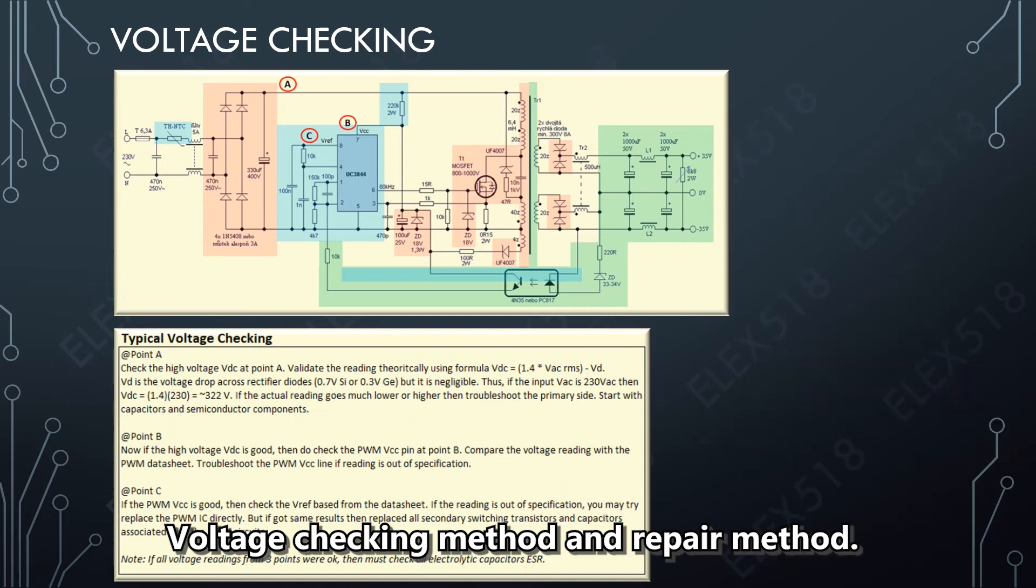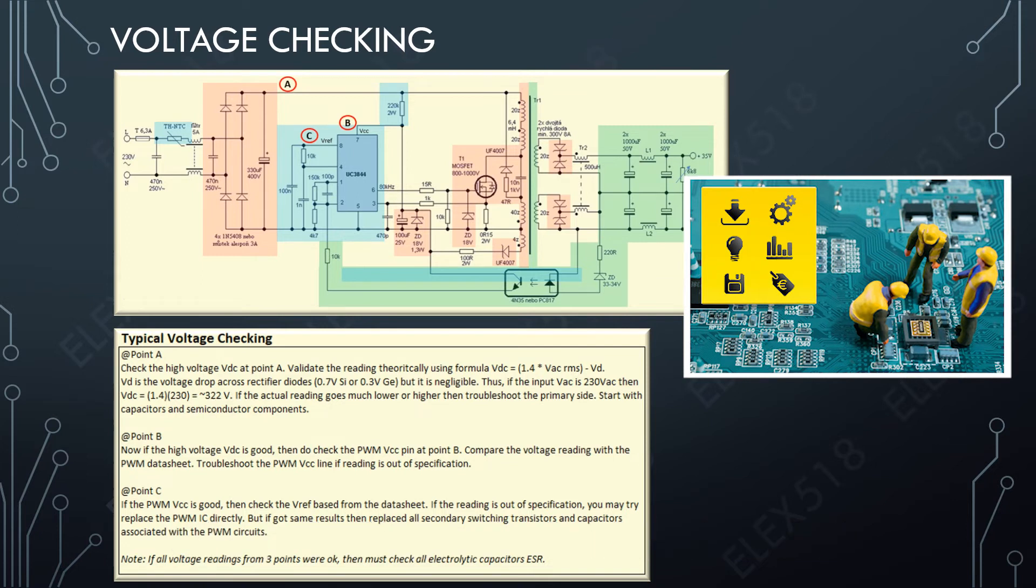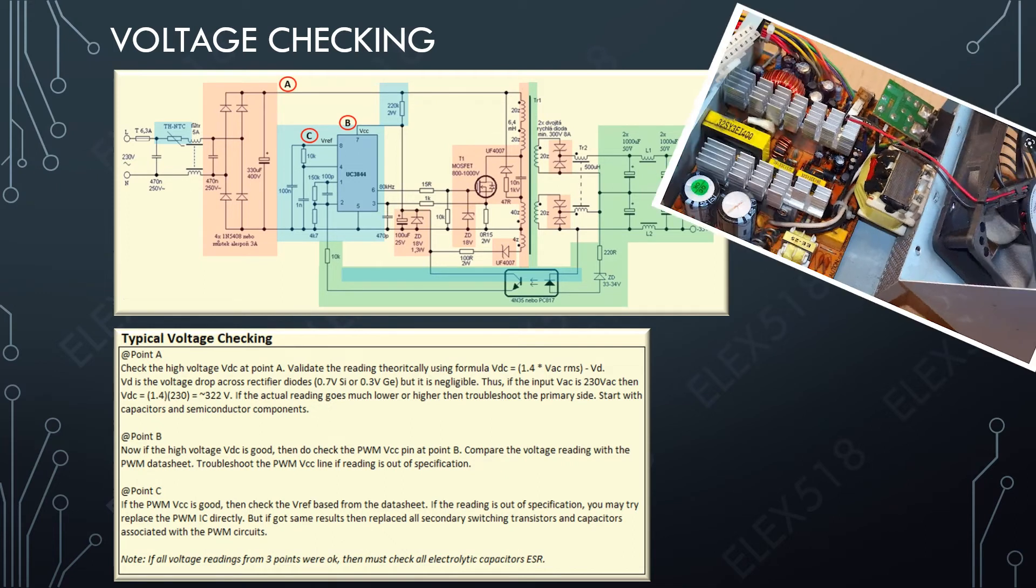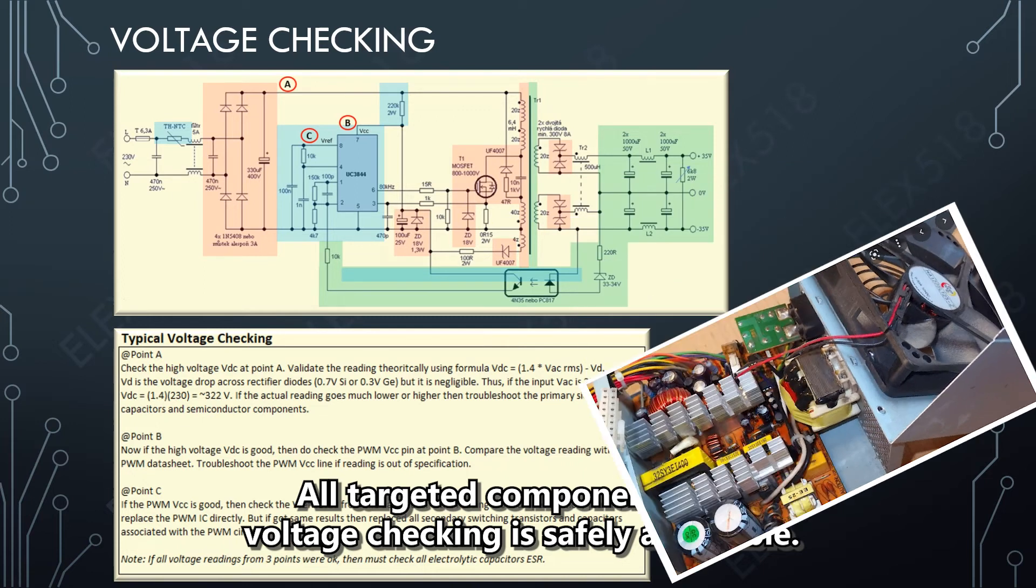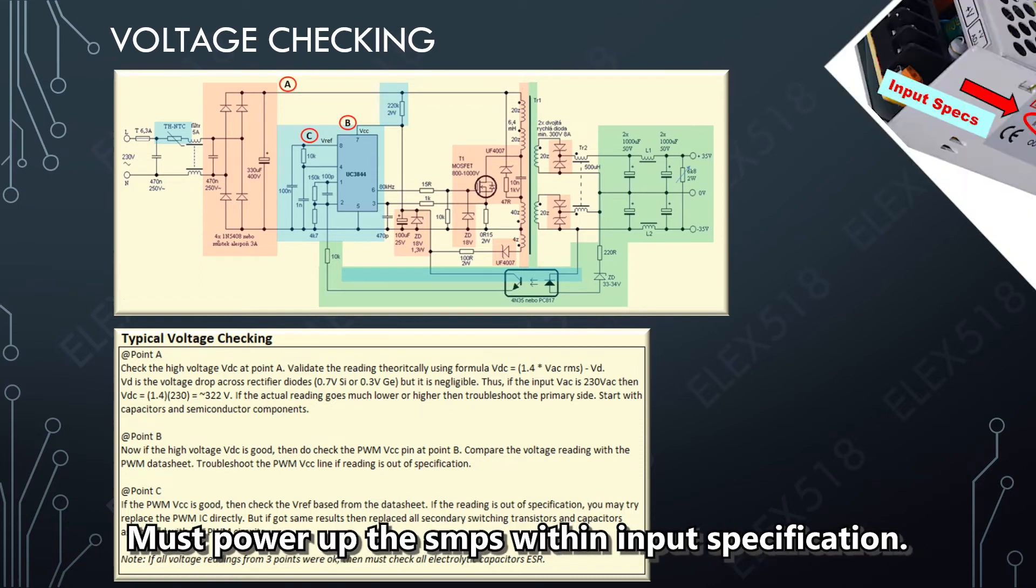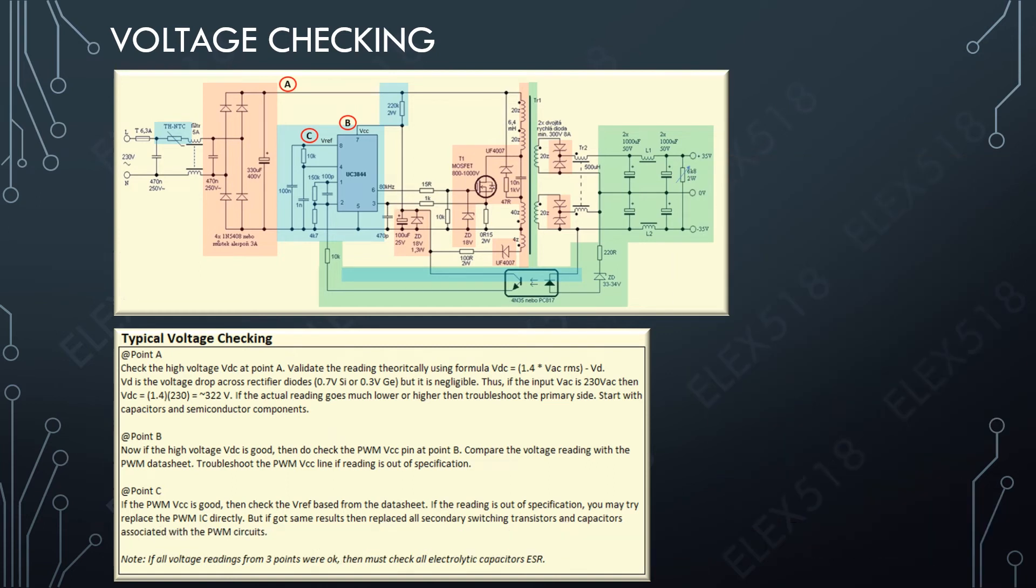In this slide I want to share the initial voltage checking and repair flow that we do before we go deeper in troubleshooting. Of course at first I need to remove the cover and make sure I get access to the components for voltage checking. I also need to power up the power supply based on input specification. Please take note of point A, point B, and point C, because these are targeted points for our initial voltage checking.